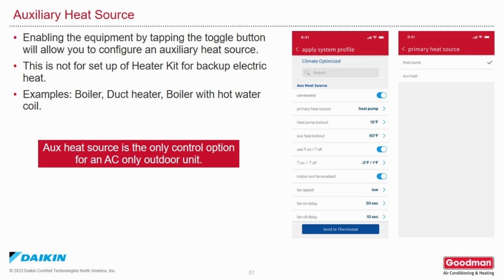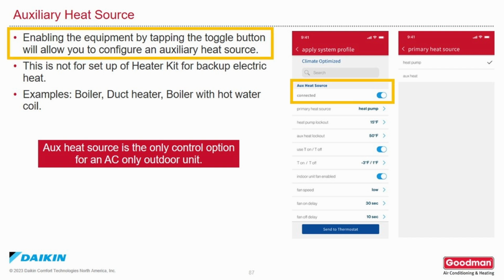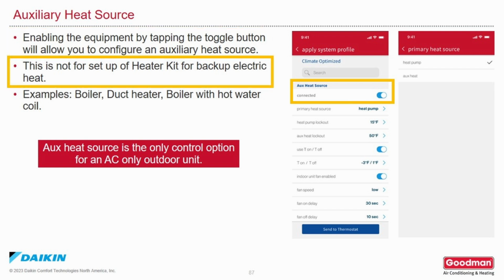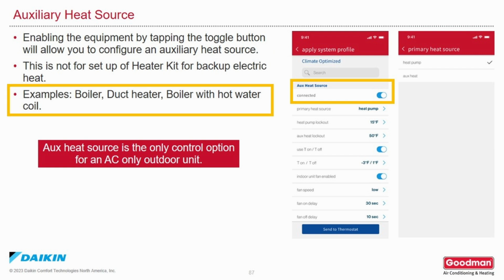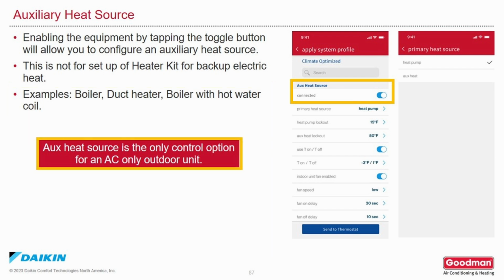For auxiliary heat source, enabling the equipment by tapping the toggle button will allow you to configure an auxiliary heat source. This is not for setting up a heater kit for electric backup heat. This is used for setting up a backup heat source such as a boiler, a duct heater, or a boiler with a hot water coil. Auxiliary heat source is the only control option for a cooling-only outdoor unit.